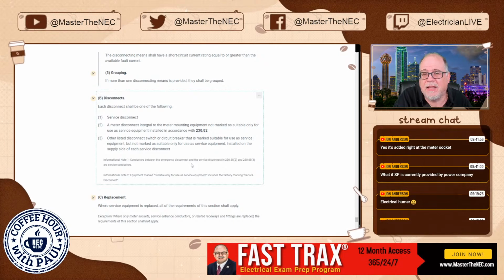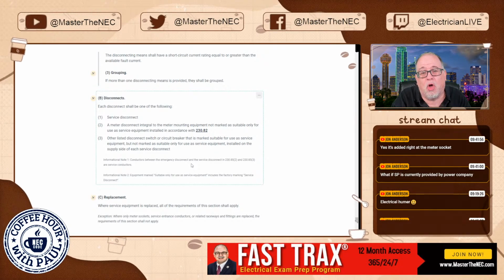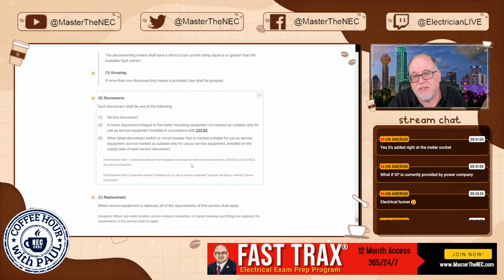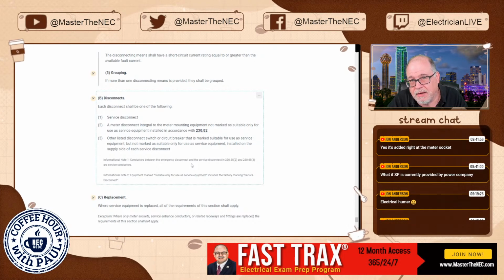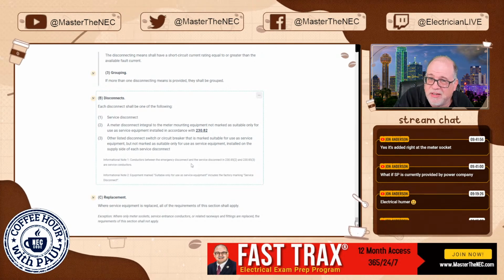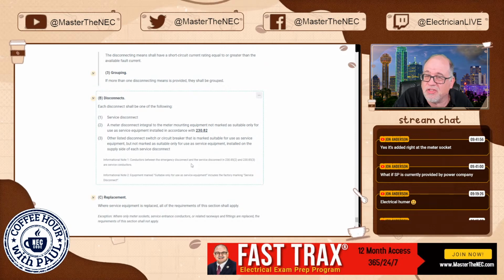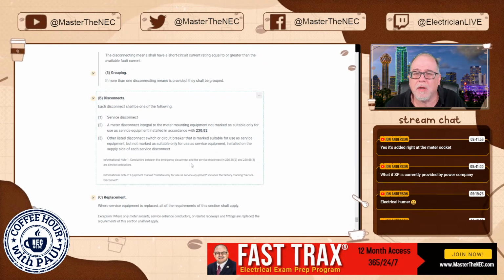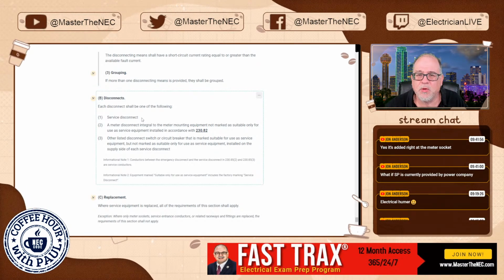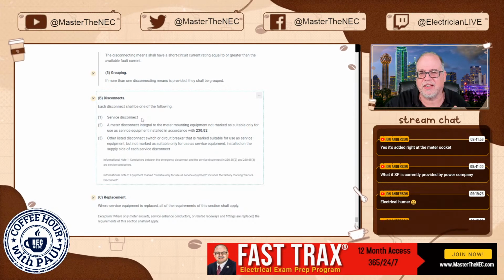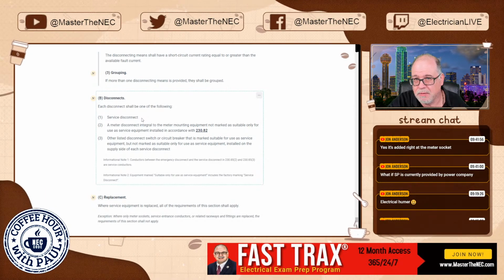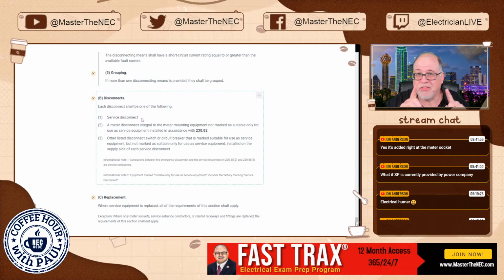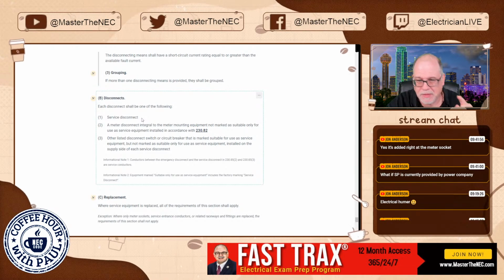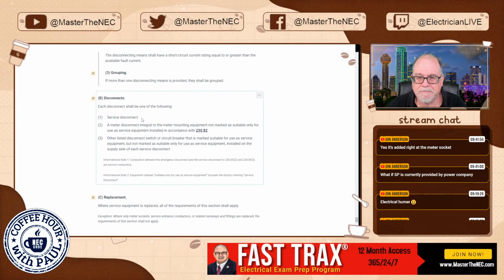Okay, and that means that you still have all the rules for the service disconnect that have to be met. Okay, remember, that's just an emergency disconnect rule. It doesn't turn it into a feeder. The only one that turns it into a feeder is if you happen to place the service disconnecting means outside. These other options, they're just emergency disconnects. Keep that in mind, okay?